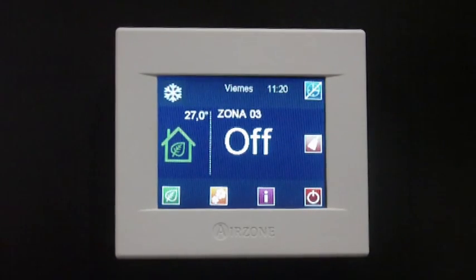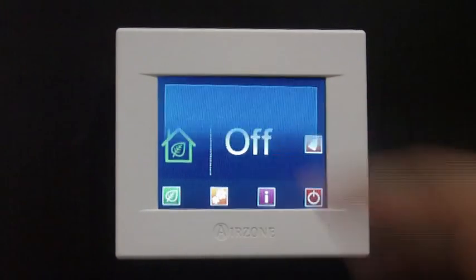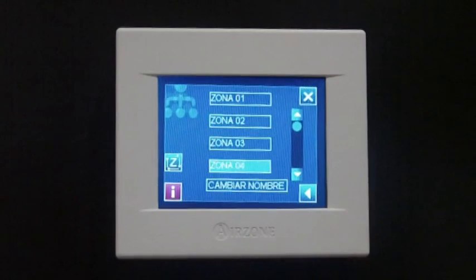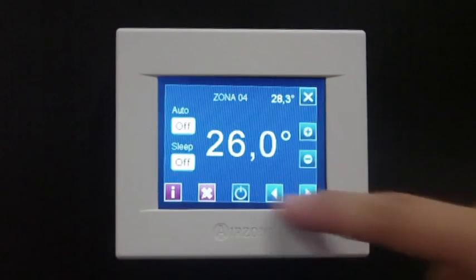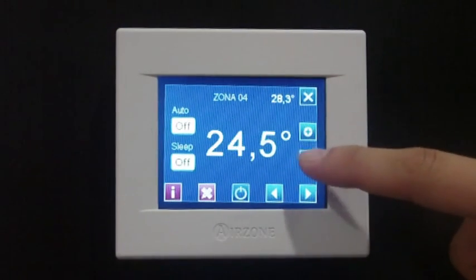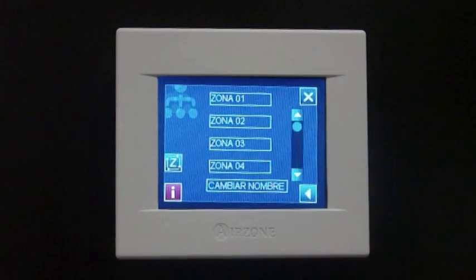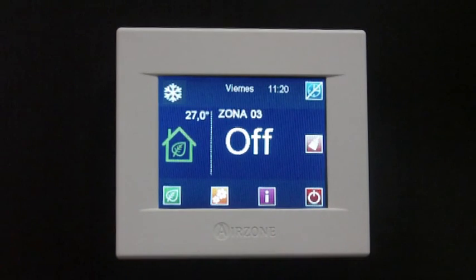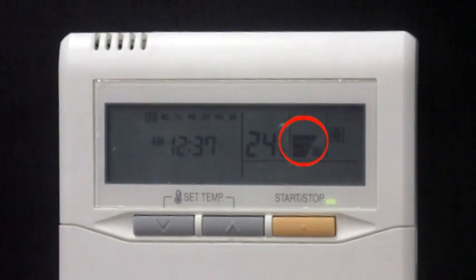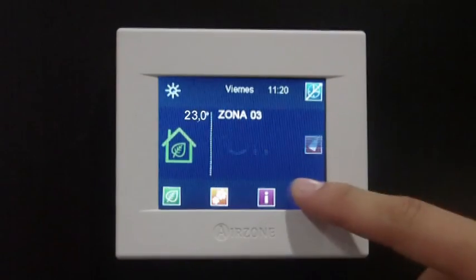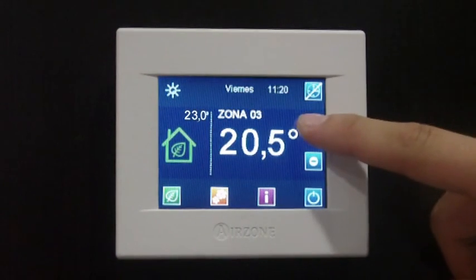The Airzone communication gateway also sets the indoor unit fan speed so that the performance of the system is adjusted according to the dynamic behavior of the installation. Hence, when there is one zone in demand, the system will set the indoor unit fan speed to the minimum available. If the number of zones on demand increases, the indoor unit fan speed will increase accordingly.